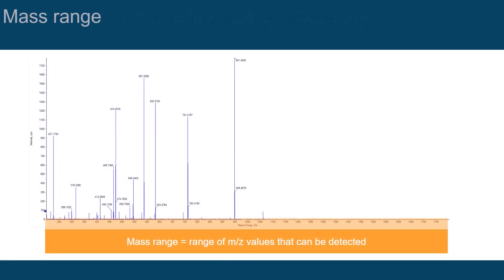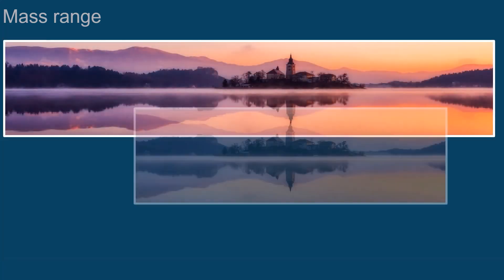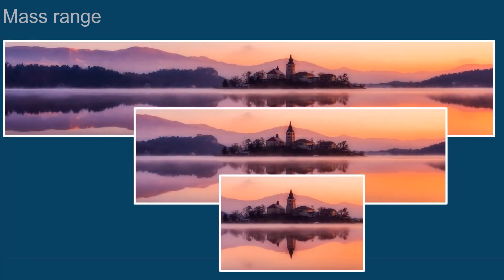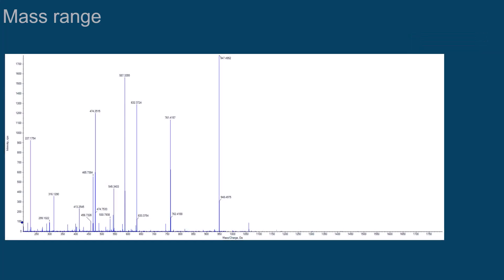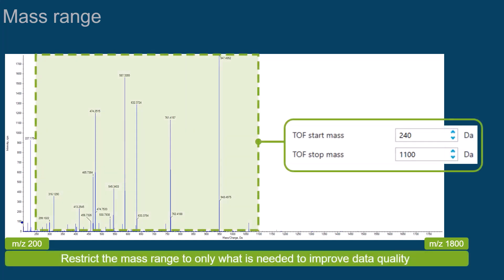Each type of mass spectrometer has a characteristic range of M over Z values that can be detected. You can compare this to the area that can be captured with wide-angle or zoom lenses. In practice, you can actively determine in which part of it ions are actually allowed to enter the mass spectrometer and thus being recorded. In this example, the mass range was recorded between M over Z 200 and M over Z 1800. Restricting the mass range only to what is needed for analysis can improve data quality.